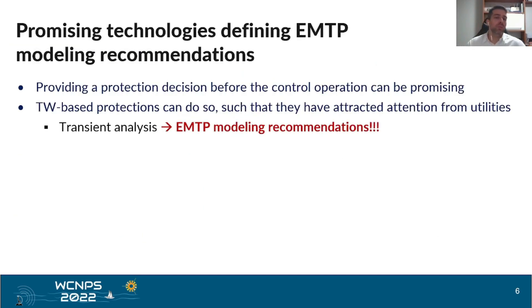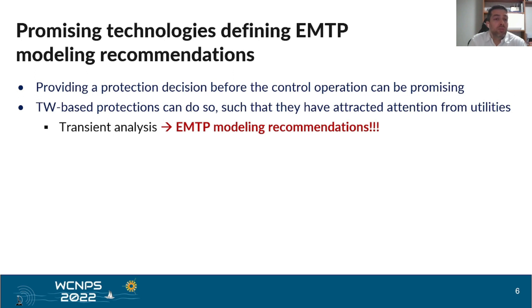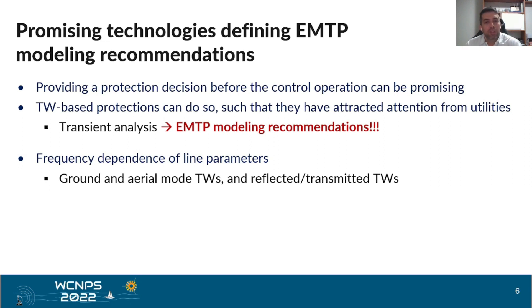Considering these problems, we also want to emphasize that there are some promising technologies which are defining the EMTP modeling recommendations. We consider that we have already proven the need for EMTP to analyze protection in the presence of IBRs. For instance, providing a protection decision before the control operation can be promising, and traveling wave-based protections can do so, which has attracted attention from utilities. In this case, we are interested in transient analysis, so there are EMTP modeling recommendations to be respected. Among them, we would like to emphasize the frequency dependence of line parameters, which must be represented because ground and aerial mode traveling waves, as well as reflected and transmitted traveling waves, are affected by such frequency dependence.